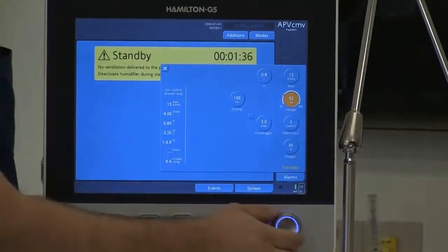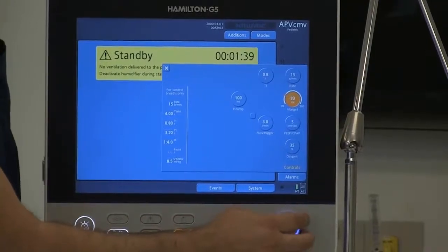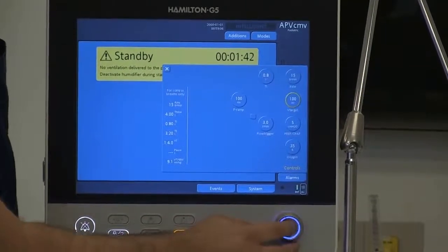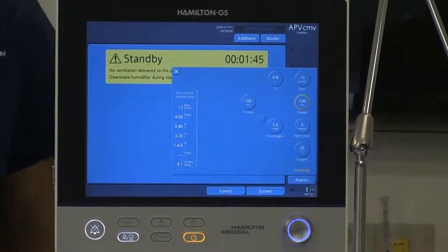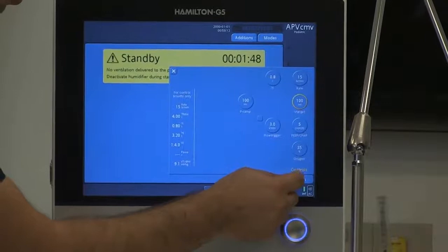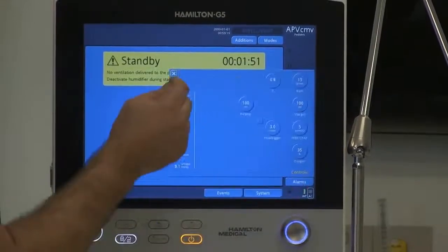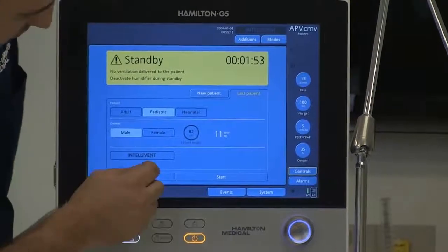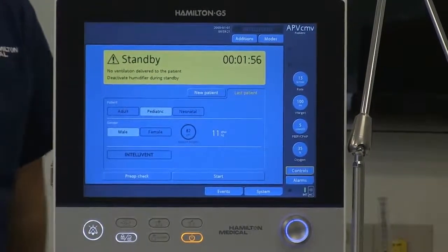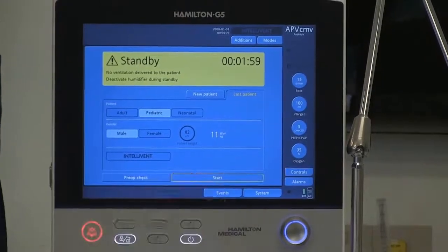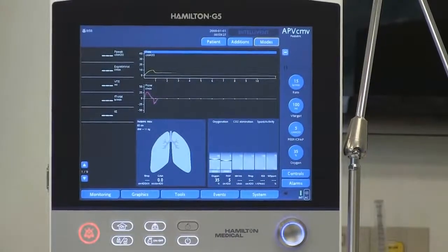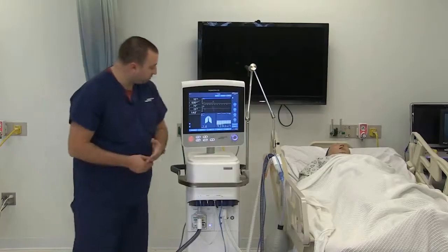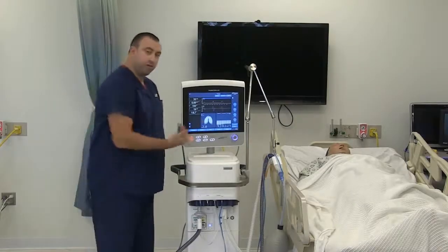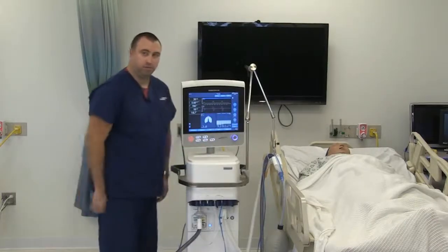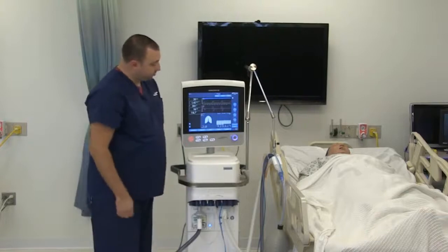Same thing with tidal volume. Once you begin to adjust it, you'll notice down here, your tidal volume is adjusted per ideal body weight. Once you have your settings plugged in, you would hit confirm. Whoops. By Xing out. And then when you're ready to place the patient on the ventilator, you would hit the start button. This is your initial screen when the ventilator starts up. All monitor parameters are on the left. All set parameters are on the right. Starting clockwise at the top and going around.